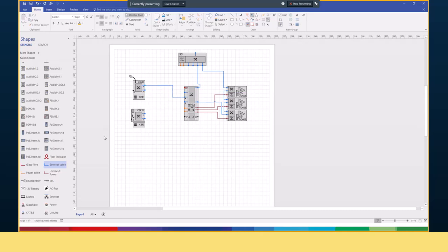There's nothing you can do about it, that is VISIO. Another one for the call station. And you see that if you have only one MPS and two call stations, you never can have a redundant power connection, because already you see that the two PoE outputs there are connected to different call stations.